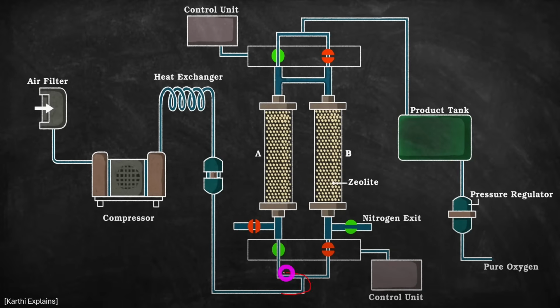First, this path is open, allowing the high pressure air to enter this zeolite structure, and this valve here is closed. As you force the air with pressure through the zeolite, it's going to absorb a lot of the nitrogen, and the oxygen is going to come out the other side. In this case, it's going to go over here, and it's going to go out into our product tank. So here we're going to have high purity oxygen beginning to be stored. Now at some point, this zeolite structure, depending on the size of this particular can over here, is going to get saturated with nitrogen, and it will not be able to absorb any more. Essentially, it's going to get clogged, but this time with nitrogen gas. So as a result of that, we need to somehow replenish it and empty it.